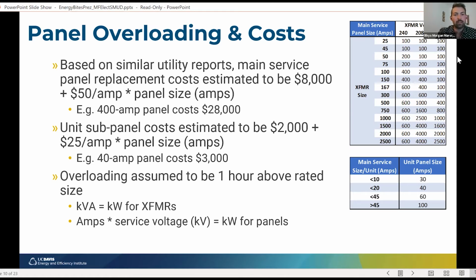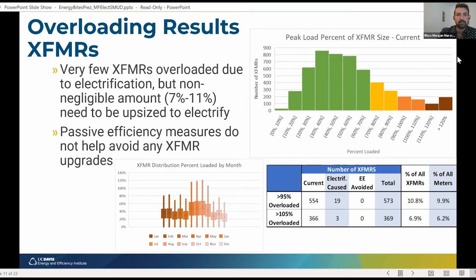And so we should take those numbers with a grain of salt. I assumed overloading meant 1 hour above the rated size of the transformer or the panel, based on the load profile that we have. I also assumed that kVA was equivalent to kW for transformers, just to make it simple, and that amps times service voltage was equal to kW for the panels. So here are the results of the transformer loading cases. There's a lot going on here, but I'll point you to the histogram on the right. You'll see that the peak load on most transformers is not above 70–75% of the rated size.